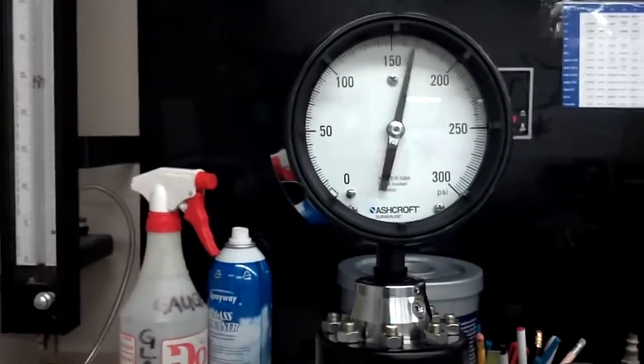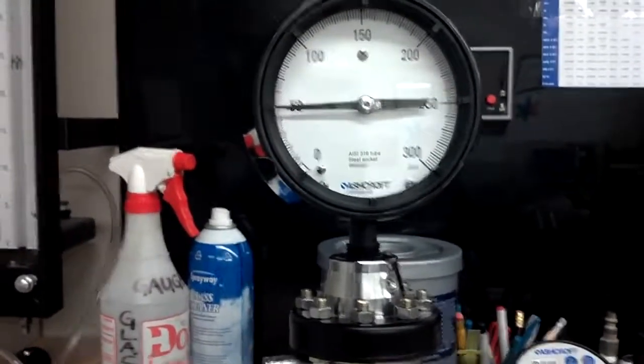Check to make sure it doesn't have any weird hysteresis going on. 150, 150, right on. Check it once more at 50. Yeah, that's right on. And this guy's ready to go. We'll box it up and send it out.